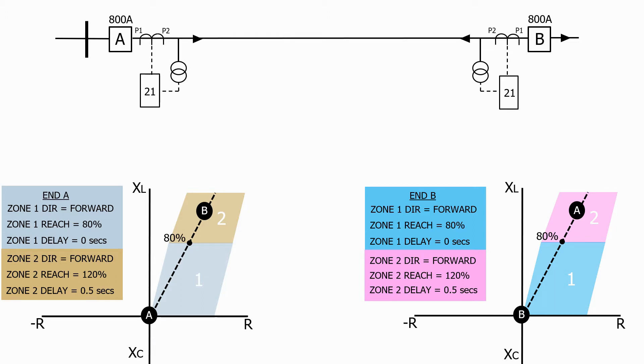To overcome the issue we had before of delayed tripping for a fault in the first and last 20% of the feeder, we provide communication between the two impedance relays. Let's now see how this works.